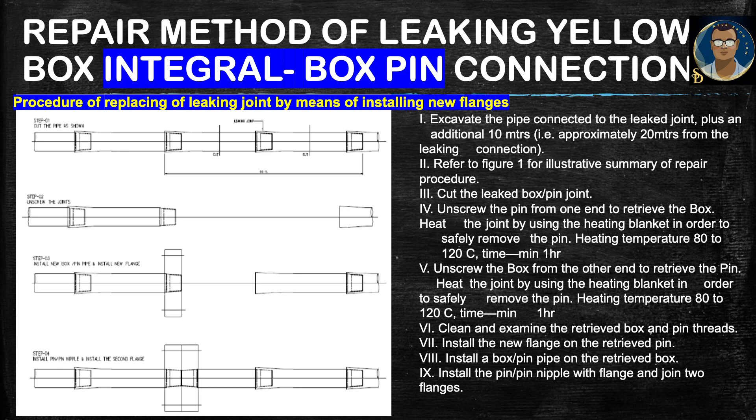Refer to the figure for an illustrative summary of the repair procedure. Cut the leaked box and pin joint. Unscrew the pin from one end to retrieve the box, then heat the joint using a heating blanket to safely remove the pin — heating temperature 80 to 120 degrees centigrade for a minimum of one hour. Unscrew the box from the other end to retrieve the pin, heating at 80 to 120 degrees centigrade for a minimum of one hour.